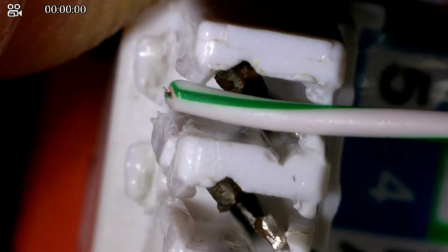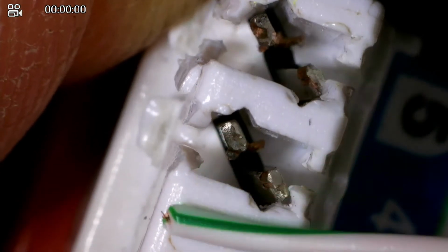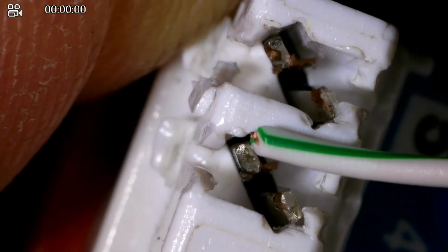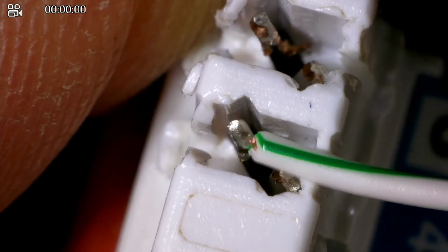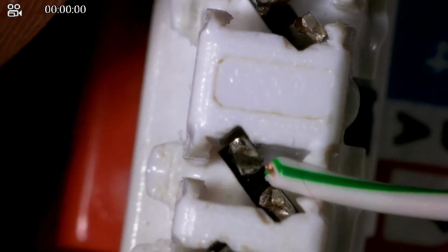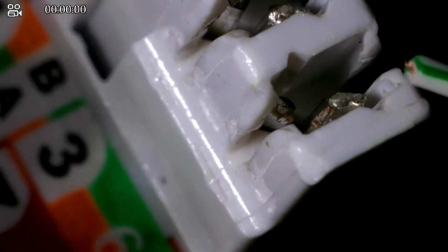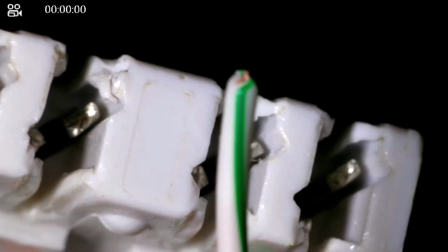If we put the wire here, you see that, and we push the wire in, these two parts of the connector are close enough that they're going to bite into the insulation and make a connection with the copper that is inside. There you go, just like that. Except we're going to put this in the groove here, and then push it down with something that's called a punch down tool.